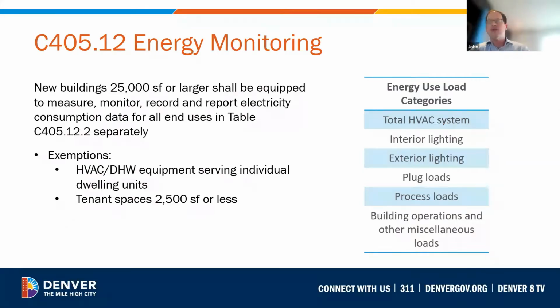Under section C405.12 of the code, there's a new requirement for electrical energy monitoring as a mandatory requirement for all projects. This requirement requires electrical consumption data of various energy use load categories to be measured, monitored, recorded, and reported separately for new buildings 25,000 square feet and larger. So the energy use load categories identified are HVAC, interior lighting, exterior lighting, plug loads, process loads, and other miscellaneous loads. Could be a pool or could be an elevator for the miscellaneous loads.